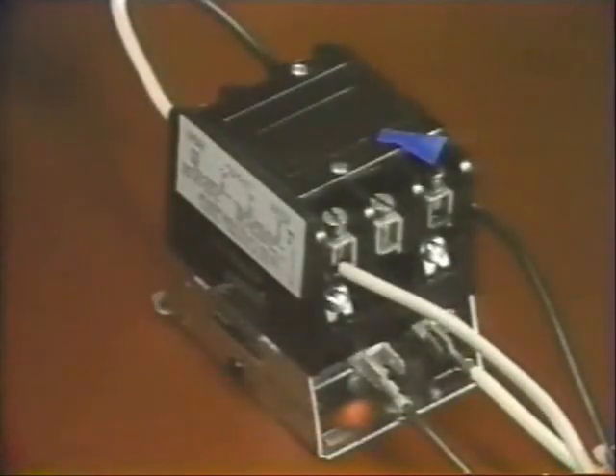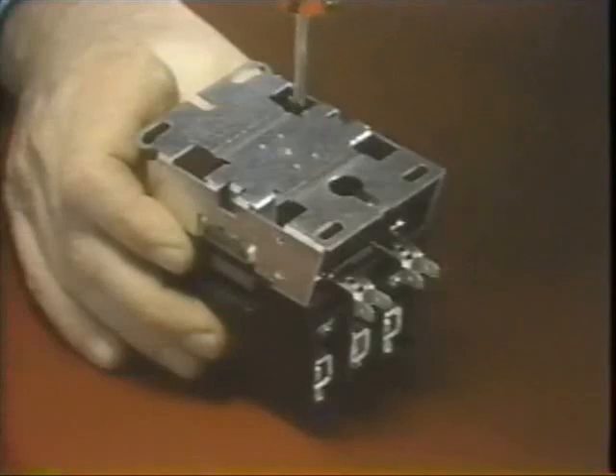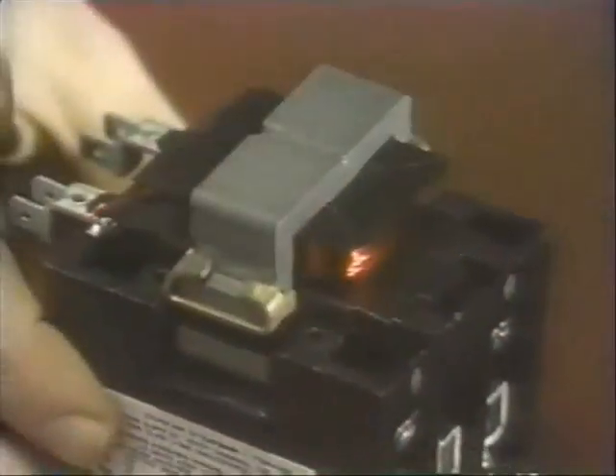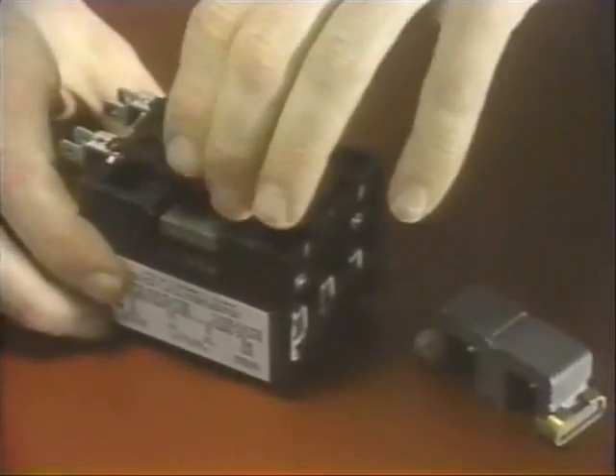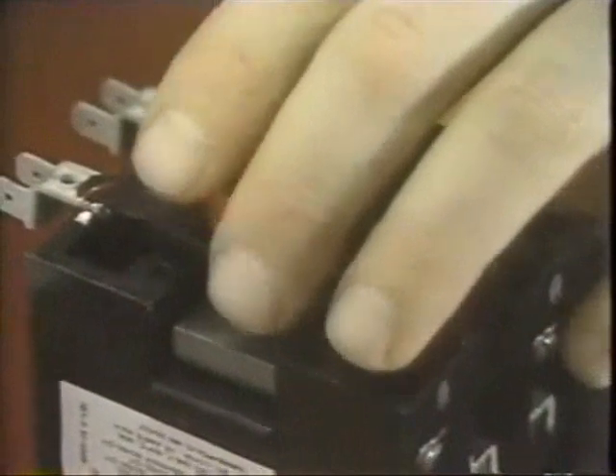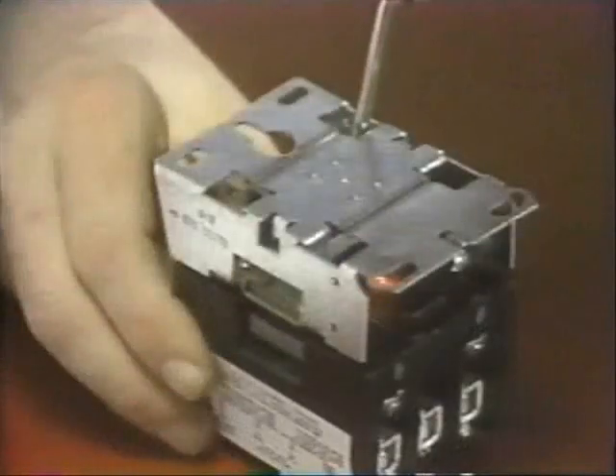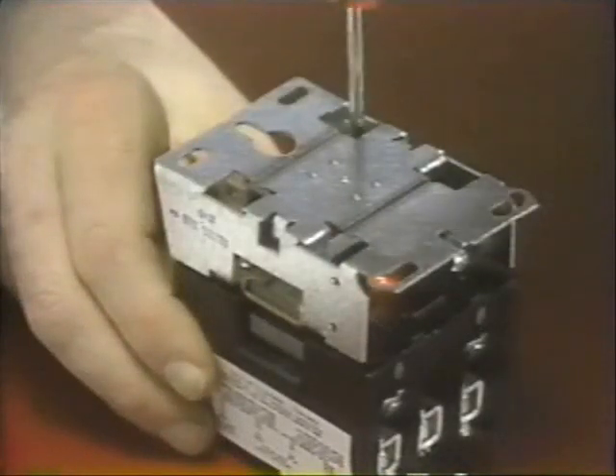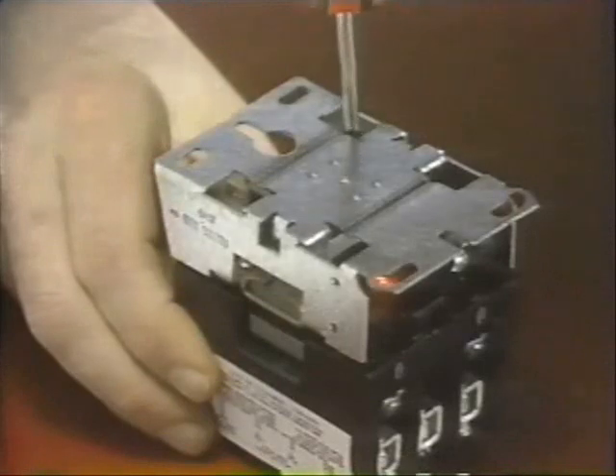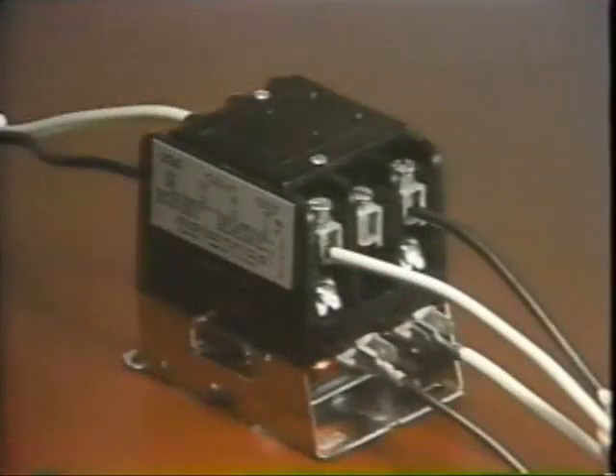Disconnect the power and remove and label all the wiring connections. Remove the screws from the mounting plate. Carefully take it apart. Note the position of the coil terminals. Carefully insert the replacement coil. With the magnet lamination nested in the base, replace the base on the arc box and firmly fasten the screws. Restore power and check contactor operation.